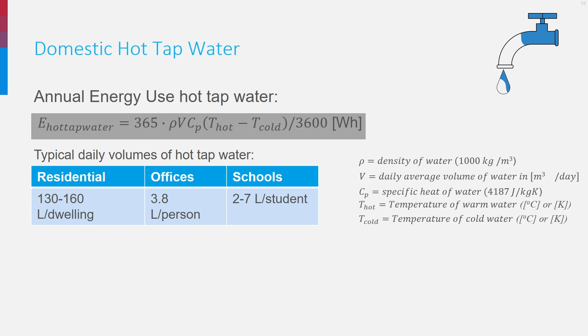In the Netherlands, we assume the temperature of cold water, T-cold, to be 10 degrees on average. A temperature T-hot of 45 to 50 degrees is enough to deliver hot water. However, many systems are continuously heated to 60 degrees to avoid the growth of Legionella.